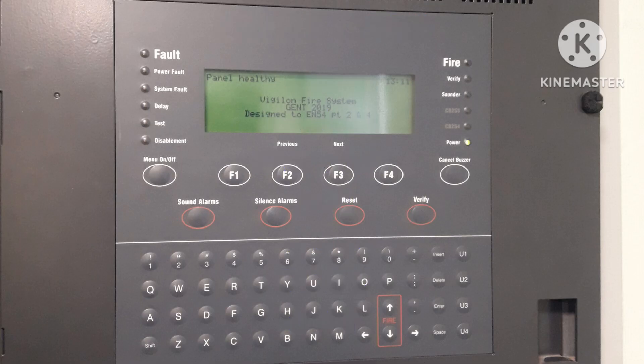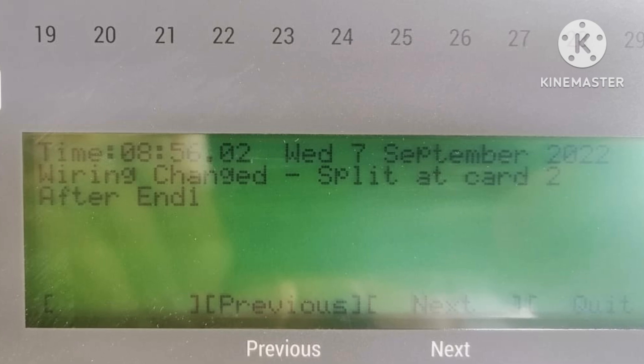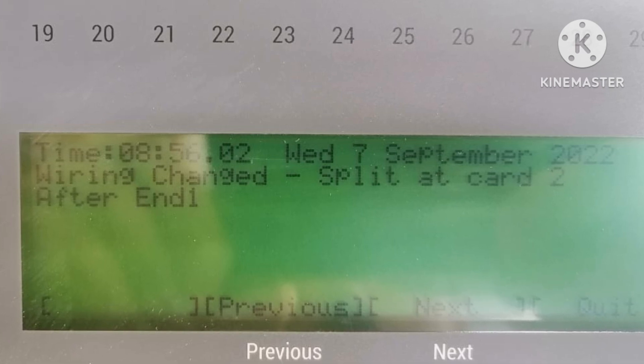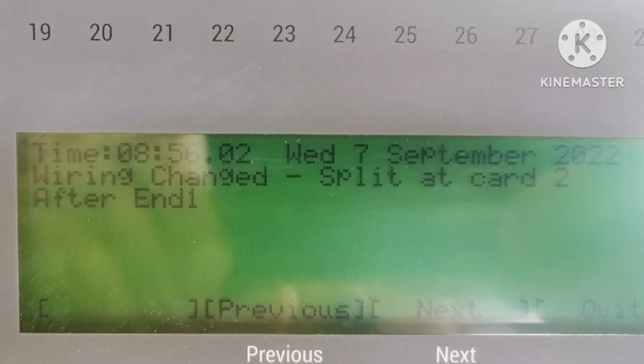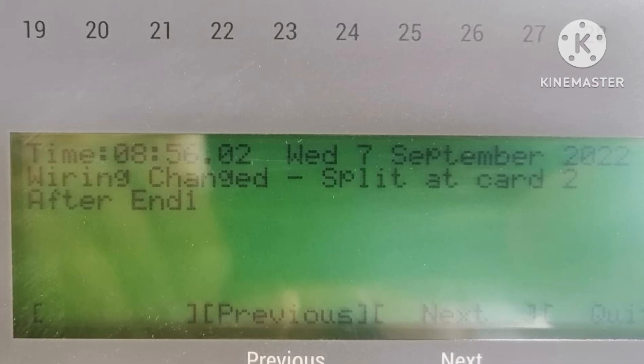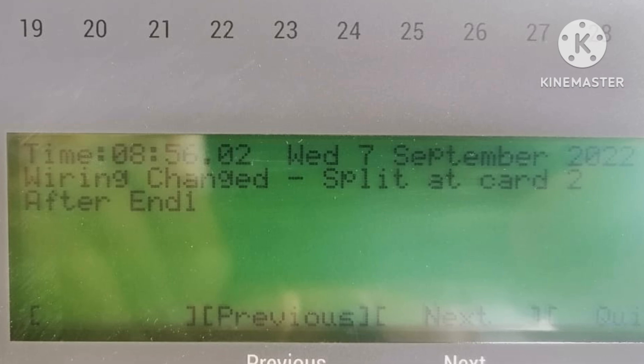So guys, for the 'loop stopped at card' fault, follow all these troubleshooting steps. But if nothing works — you remove everything, bypass all the devices — and it is still not relocating, it means your loop card has a problem and may be damaged. Thanks for watching.